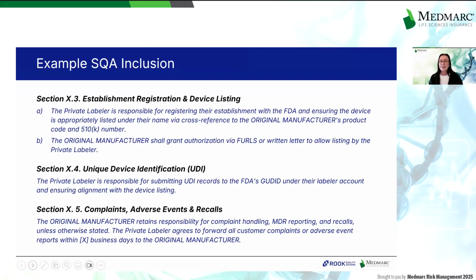into Section X.3, Establishment Registration and Device Listing. The private labeler is responsible for registering their establishment with the FDA and ensuring the device is appropriately listed under their name via cross-reference to the original manufacturer's product code and 510(k) number. The original manufacturer shall grant authorization via FURLS or written letter allowing the listing by the private labeler. Section X.4 identifies unique device identification, or UDI, requirements. The private labeler is responsible for submitting UDI records to the FDA's GUDID database under their labeler account and ensuring alignment with the device listing.